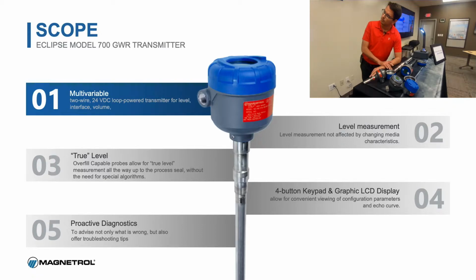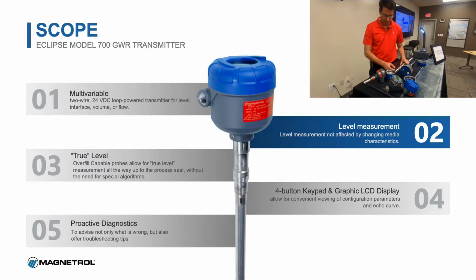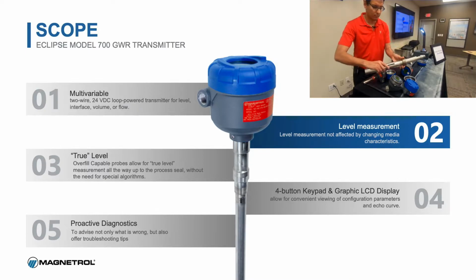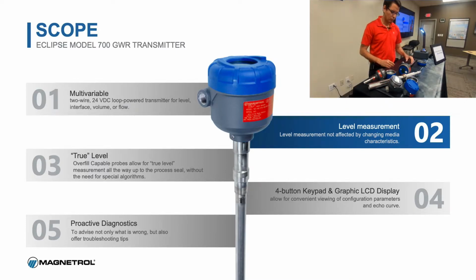So why do I refer to it as a multivariable? Well, I just said it. The transmitter, because it has the 706 firmware, could be used for a volumetric, a flow application, an interface application, not just level. The other thing, the level measurement, is a true level measurement. So here it is priced at the same performance as a differential pressure transmitter, like one of the higher quality ones, less than actually. And instead of it being an inferential measurement, it's a direct level measurement. It's actually measuring the distance to the surface of the level to the bottom of the probe. And therefore, it's not an inferential measurement, but a true measurement.